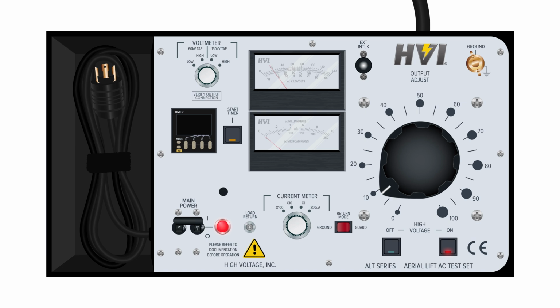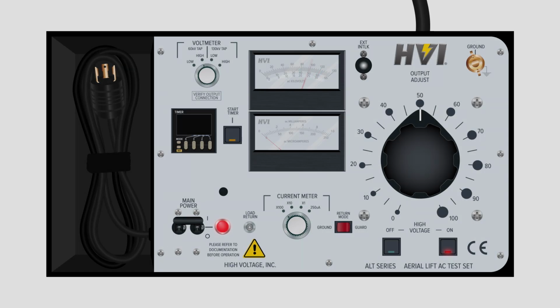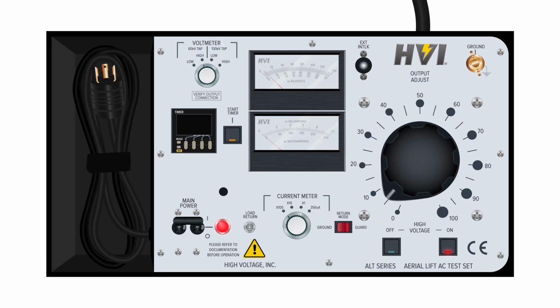tap. When the switch is set to low range for the 60 kV tap, for voltages up to 30 kV, the voltage is read from the very bottom scale. When the switch is set to high range for the 60 kV tap, for voltages up to 60 kV, the voltage is read from the middle scale. Before you switch over to the 130 kV tap ranges, you will first need to power down the device and change your high voltage output connections.